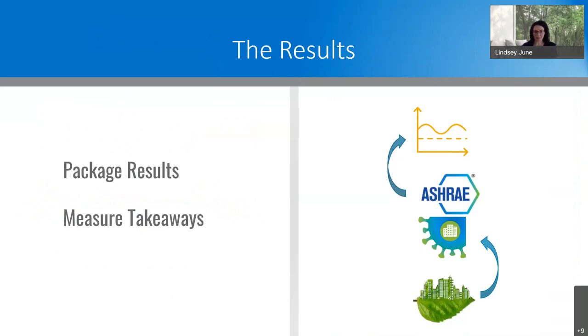So first, let's briefly refresh on the package approaches that we discussed earlier. There were two packages of improvements that were evaluated. First was the ASHRAE package, which was the energy impact compared to the pre-COVID baseline energy use and the IAQ effectiveness of any feasible measure from the guidance that's set forth by the ASHRAE Epidemic Task Force back in June of 2020. And then the energy efficiency package included strategies that enabled a more energy efficient solution compared to the ASHRAE baseline package of measures while maintaining the IAQ effectiveness of the ASHRAE package or a deemed IAQ target. All right, now let's go over the energy efficiency package results compared to the ASHRAE baseline package. Next slide.